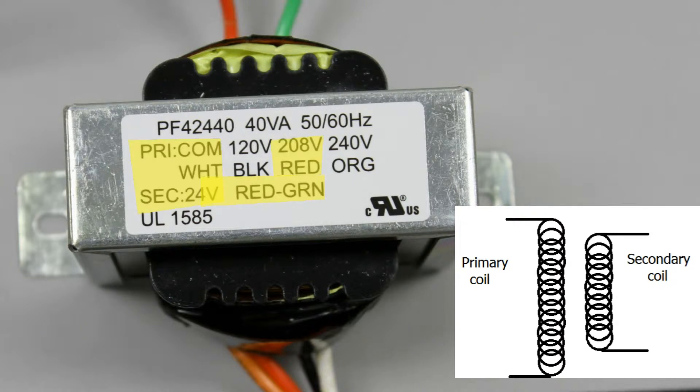If we have 208 volts, we use the red and white wire, and we'll get 24 volts out. That's about an 8 and 2 thirds to 1 ratio. If we have 240 volts, we use the white and orange. That's a 10 to 1 ratio.